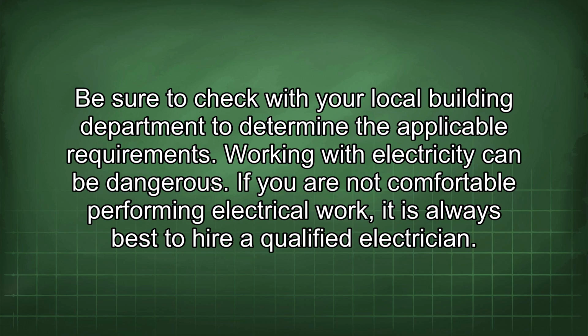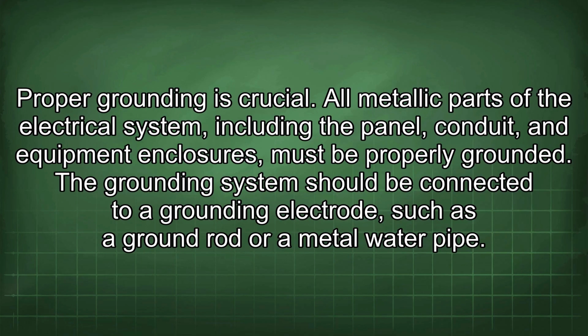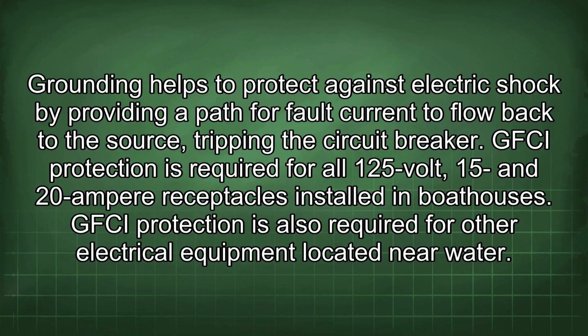Working with electricity can be dangerous. If you are not comfortable performing electrical work, it is always best to hire a qualified electrician. Proper grounding is crucial. All metallic parts of the electrical system, including the panel, conduit, and equipment enclosures, must be properly grounded. The grounding system should be connected to a grounding electrode, such as a ground rod or a metal water pipe. Grounding helps to protect against electric shock by providing a path for fault current to flow back to the source, tripping the circuit breaker.